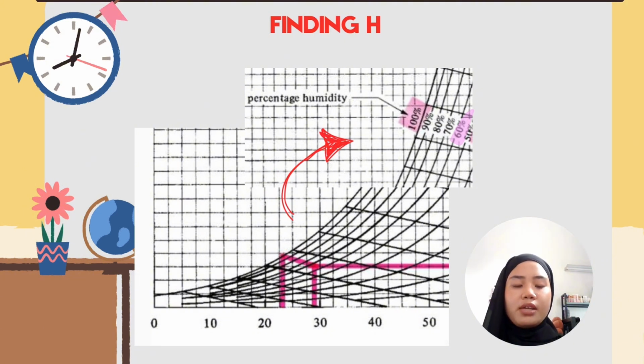From the data given, the wet bulb temperature is 23.9 and the entering air dry bulb temperature is 29.4. We plot these two temperatures into the humidity chart, drawing the line for the wet bulb until 100% since it is fully saturated, and for the dry bulb until 60% since it is constant relative humidity. Then we connect these two points.